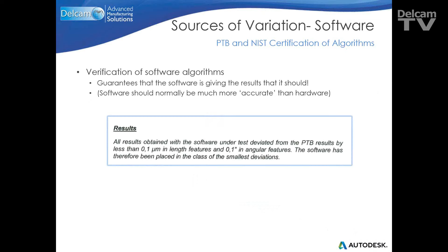Now, there are two bodies that can be used for software verification. You have the German standard body, which verifies the evaluation of spheres, planes, and cylinders, and you have the American NIST software body, which states whether or not the software is mathematically correct, and whether the software is giving you the results that it should, whether the algorithms are working correctly.